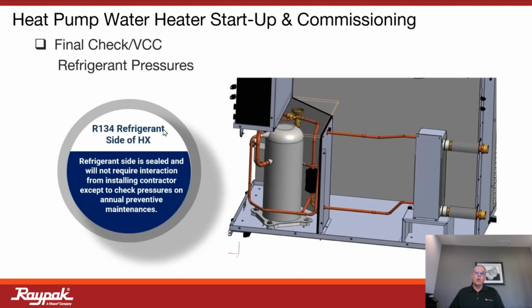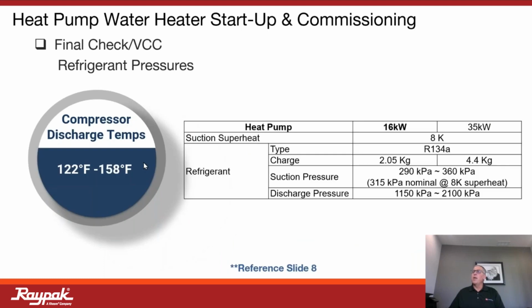In terms of the final startup and commissioning, we also completely understand and frankly fully appreciate that the refrigerant side of this process is a sealed chamber. We don't have to interact with it. That refrigerant is captured within the compressor, the piping, and this side of that brazed plate heat exchanger. But there is, on a startup and commissioning, an ability to go in and check those refrigerant temperatures and refrigerant pressures just as a visual and do that as a checkoff. So again, we're converting this over into pressure, PSI, as opposed to kilopascals. We're also converting it over into Fahrenheit as opposed to Celsius.